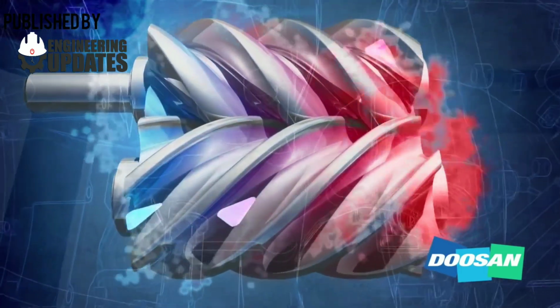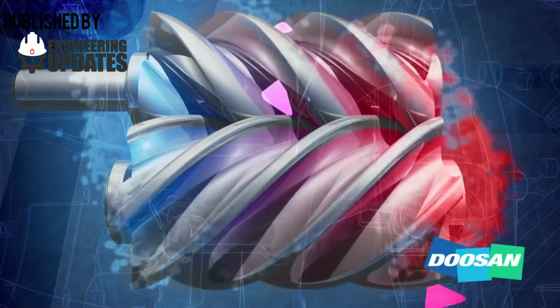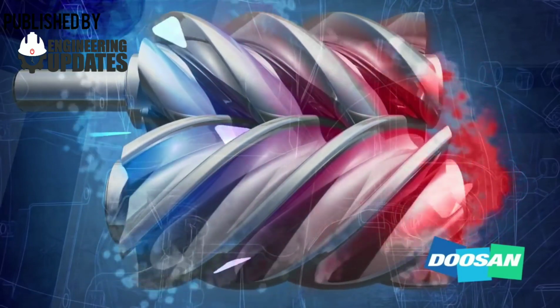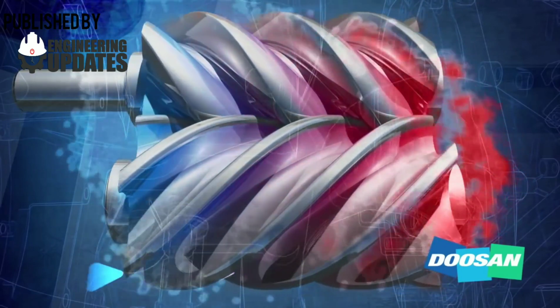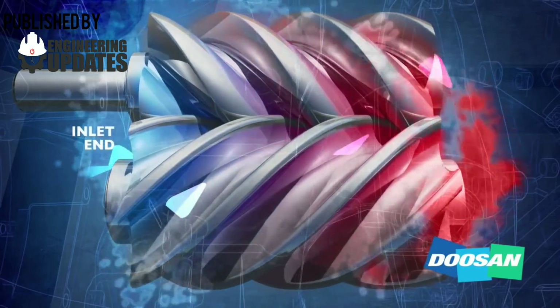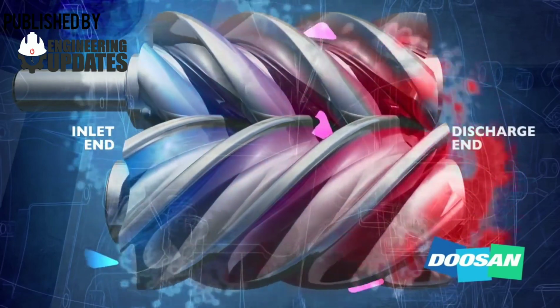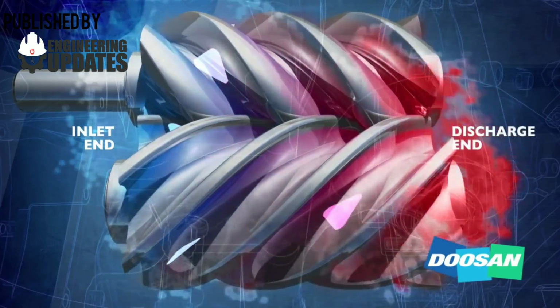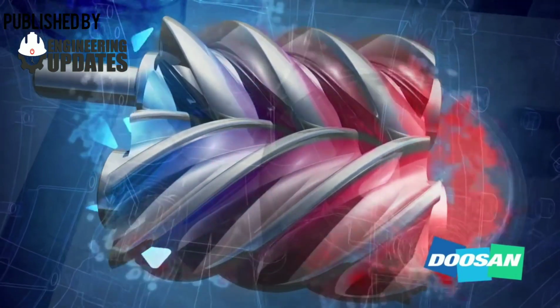As air travels along the helical rotor flutes, the space stored in the air gets progressively smaller. Since the air cavity between the rotors is larger at the inlet end and smaller at the discharge end, air becomes compressed, creating significant heat.